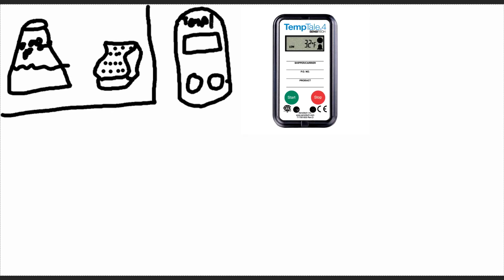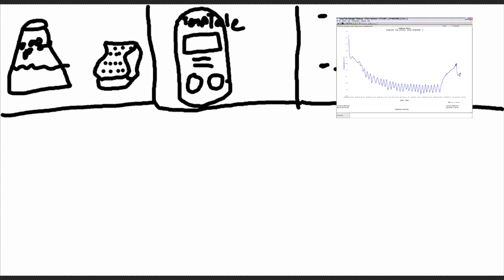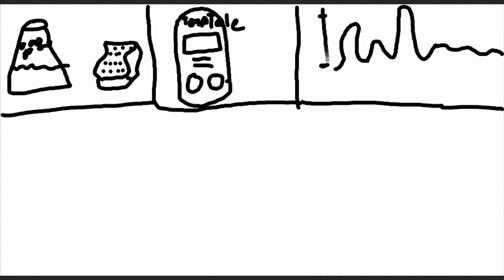During this time, I would take the daily TempTale recordings from the incubators and fridges. TempTales are devices that monitor the temperature of the environment. I would download the data from the TempTales and make sure they were within range.